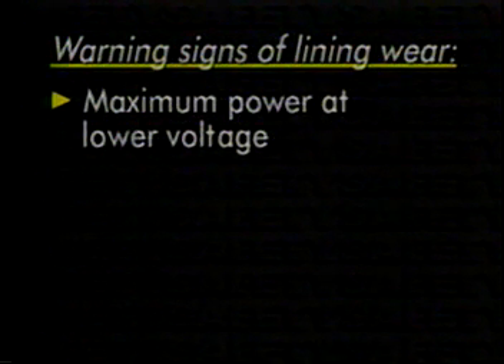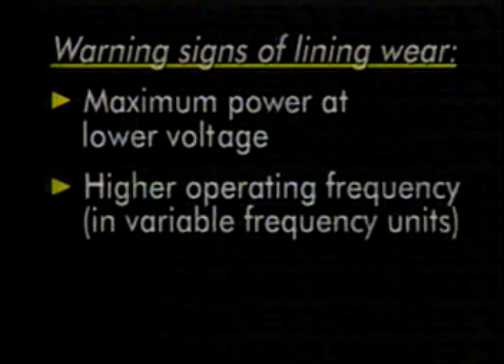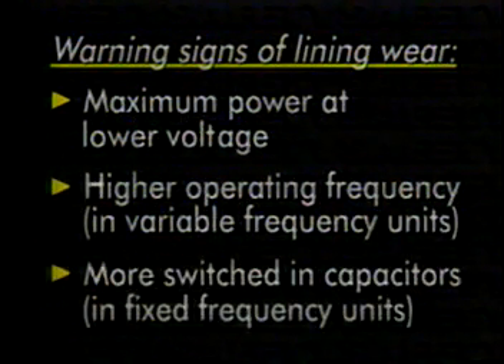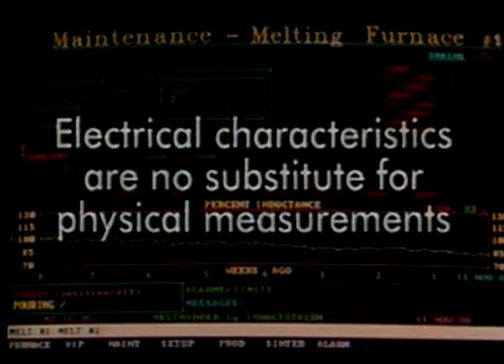In situations where frequent visual inspections of coreless furnaces are not practical, when, for example, they are used for continuous holding and dispensing, operators should remain alert for two important warning signs of lining wear: attainment of maximum power at a lower than normal applied voltage, or higher than normal operating frequency in variable frequency power supplies, and in fixed frequency units, an increase in the number of capacitors needed to be switched into the circuit to maintain unity power factor. Useful though they may be, changes in electrical characteristics must never be thought of or used as a substitute for physical measurements of the lining itself.